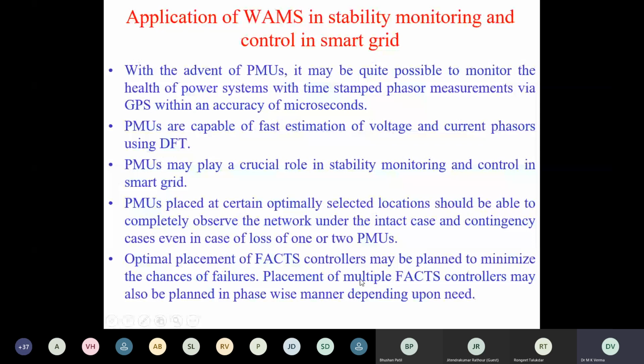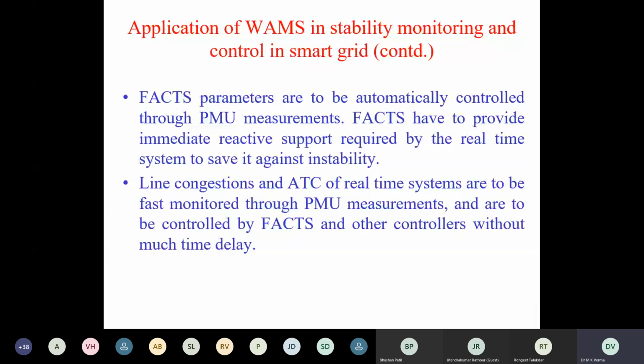And then PMUs may be helpful in security monitoring of the system. So FACTS parameters are to be automatically controlled through PMU measurements. FACTS have to provide immediate reactive support for the real-time system against instability. Line congestion and ATC of the real-time system are to be quickly monitored through PMU measurements and are to be controlled by FACTS and other controls.